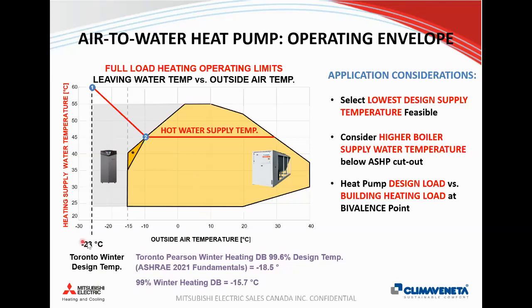So again, this is our design temperature for the city of Toronto, which is a requirement according to the building code. But whenever you look at the ASHRAE winter dry bulb heating design for 99.6%, you'll see that it's actually minus 18.5, and even the 99% value is minus 15.7.